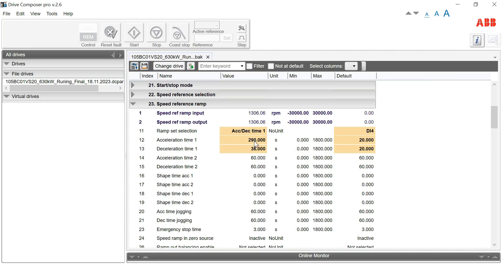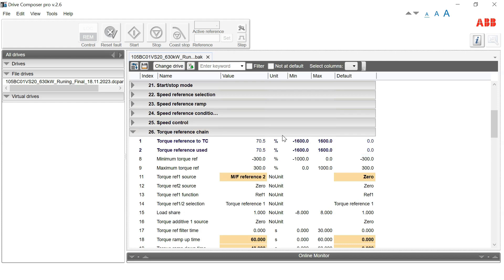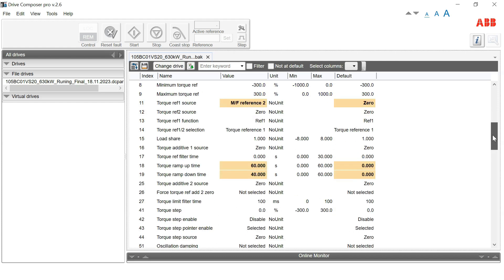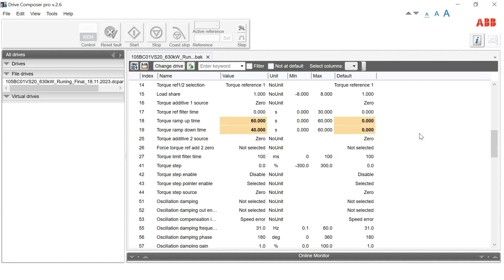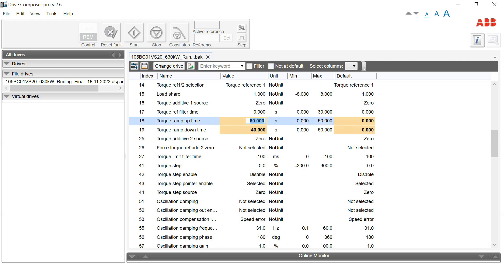So 290 seconds is almost 5 minutes to reach full speed. In the same way, the torque should also ramp up. Ramp up time means the rate at which torque increases. But as VS20 was taking low torque, it was taking more time. So you have to decrease the torque ramp time — if you decrease the time, it will change the torque faster.